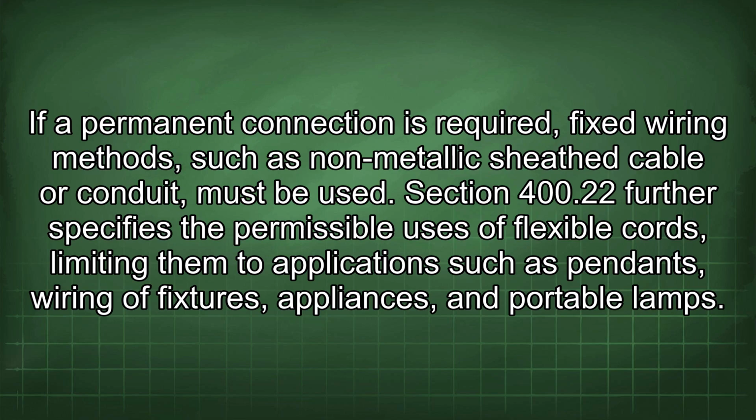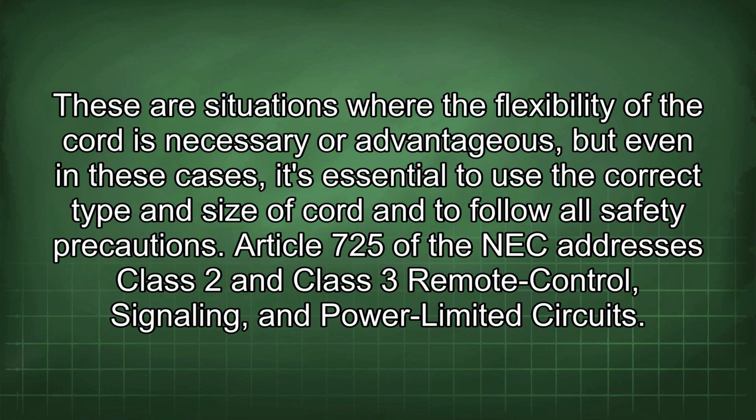Section 400.22 further specifies the permissible uses of flexible cords, limiting them to applications such as pendants, wiring of fixtures, appliances, and portable lamps. These are situations where the flexibility of the cord is necessary or advantageous, but even in these cases, it's essential to use the correct type and size of cord and to follow all safety precautions.